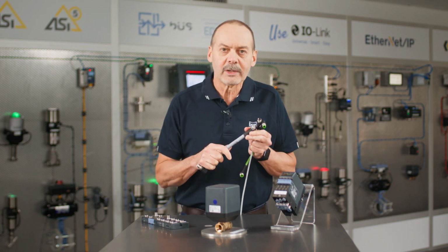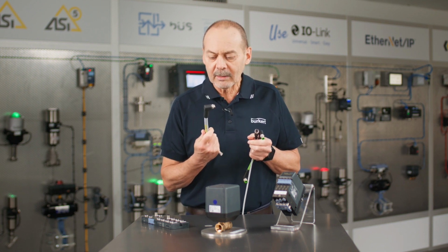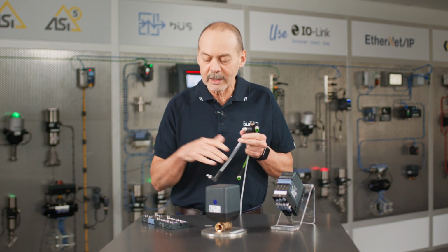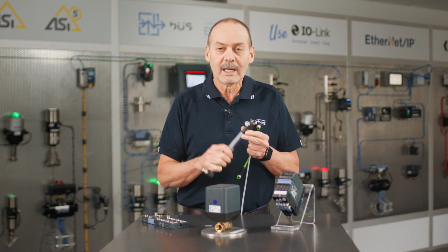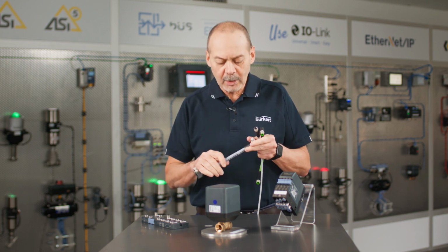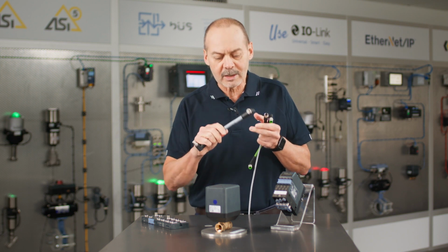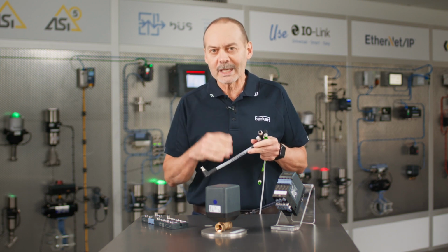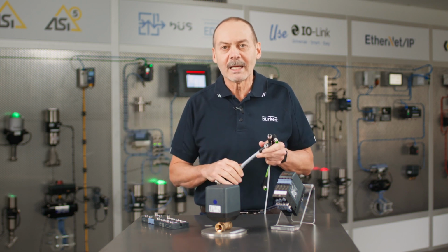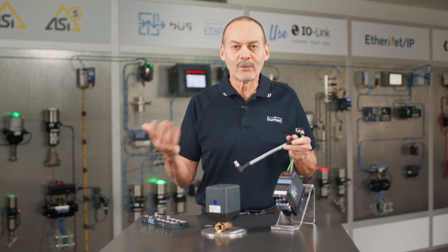Most of the L-coded power you see in the market is just 1.5 square mil. Now, when you're running 24 volts, especially over I/O platforms, when you're connecting lots and lots of I/O, 1.5 square mil we've found doesn't always cut it. So Bürkert has a specific 2.5 square mil which we like to standardize on where possible. Just to give you an example, if you're to run just 6 amps across 20 meters, then the 1.5 square mil will drop about 4 whole volts.